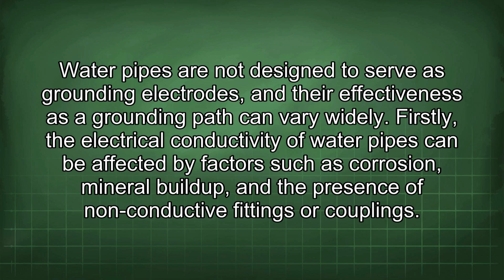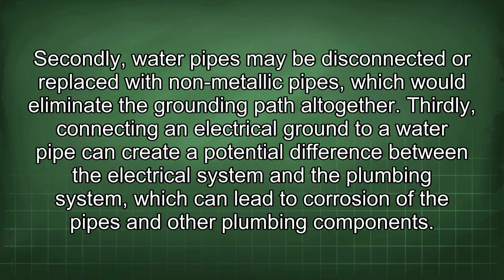Firstly, the electrical conductivity of water pipes can be affected by factors such as corrosion, mineral buildup, and the presence of non-conductive fittings or couplings. Secondly, water pipes may be disconnected or replaced with non-metallic pipes, which would eliminate the grounding path altogether. Thirdly, connecting an electrical ground to a water pipe can create a potential difference between the electrical system and the plumbing system, which can lead to corrosion of the pipes and other plumbing components.